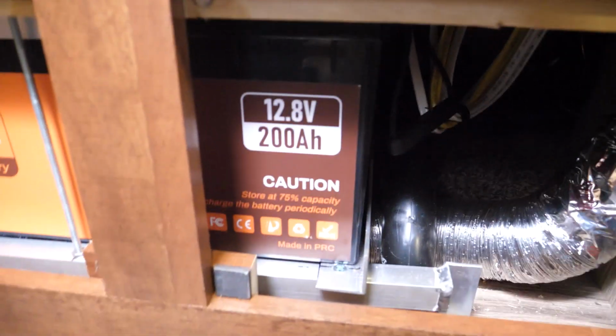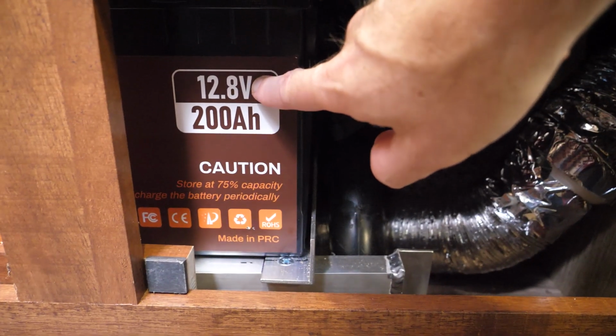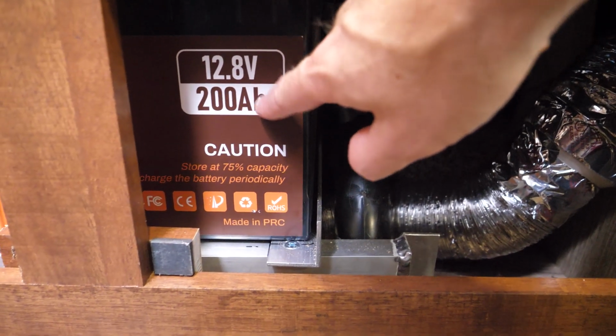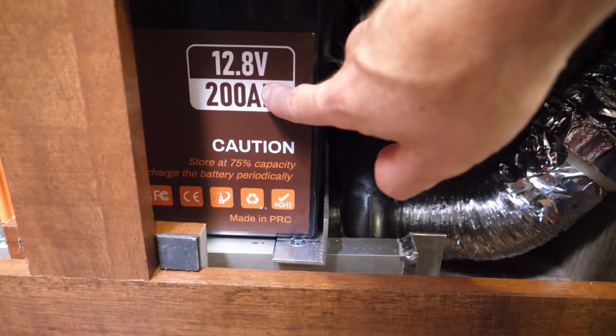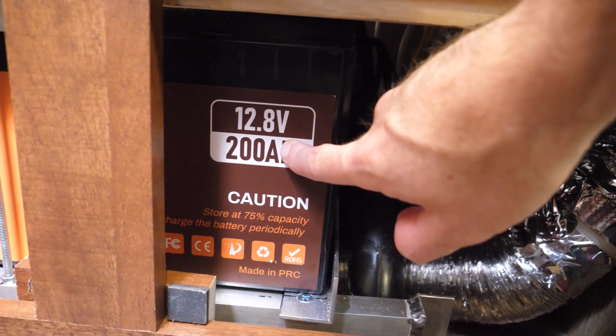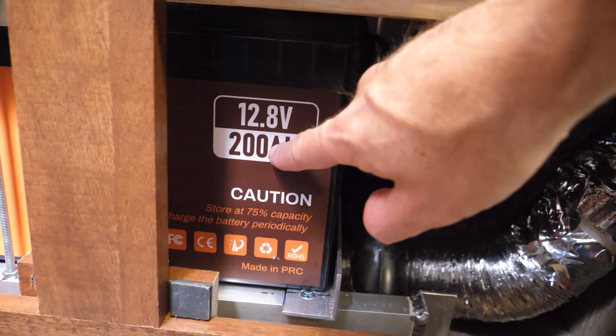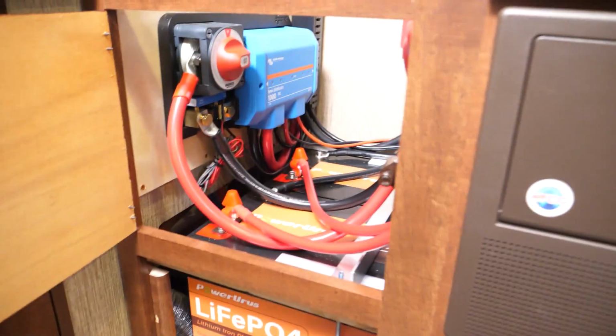So it's 200 amp hour, 12.8 volts times 200, and volts times amps is power. So 12.8 times 200, that's where this 2,560 watt hour number comes from, which is right on the battery. Because there are two of them, we add that together, which is where I'm getting that roughly 5,000 watt hours of capacity.